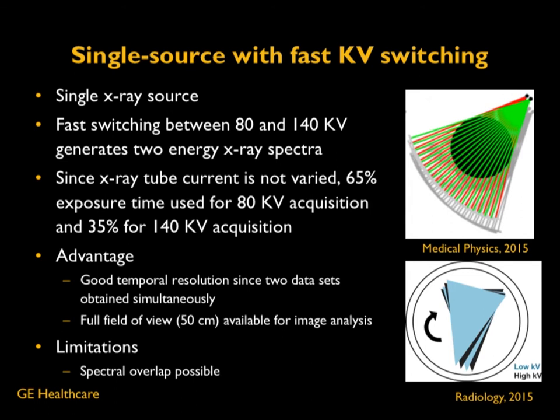The main advantage of this technique is very good temporal resolution, because the two data sets are obtained simultaneously from the same anatomical location. Another advantage is that the full field of view — approximately 50 centimeters, slightly smaller than the gantry opening — is achievable for image analysis, just as with a regular CT scanner, since it uses the same x-ray tube switching simultaneously at each point.